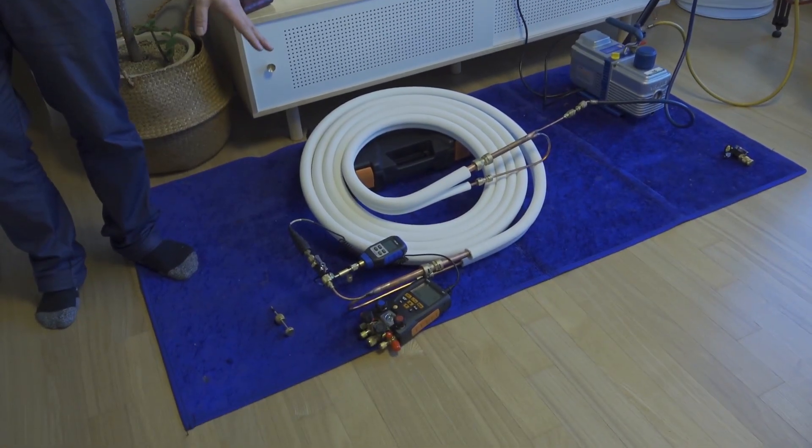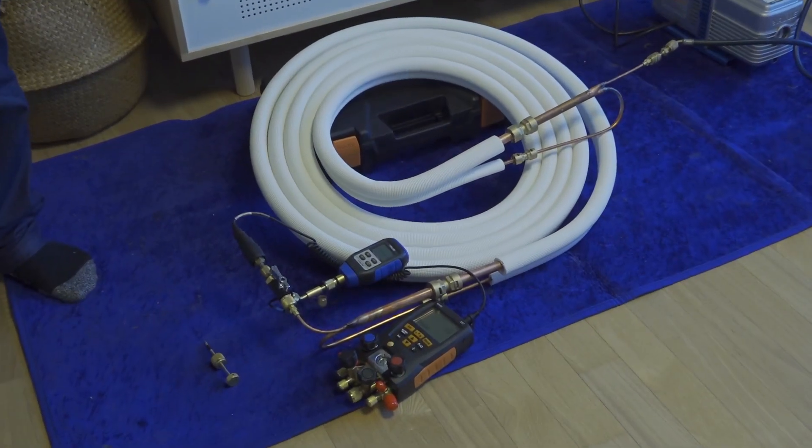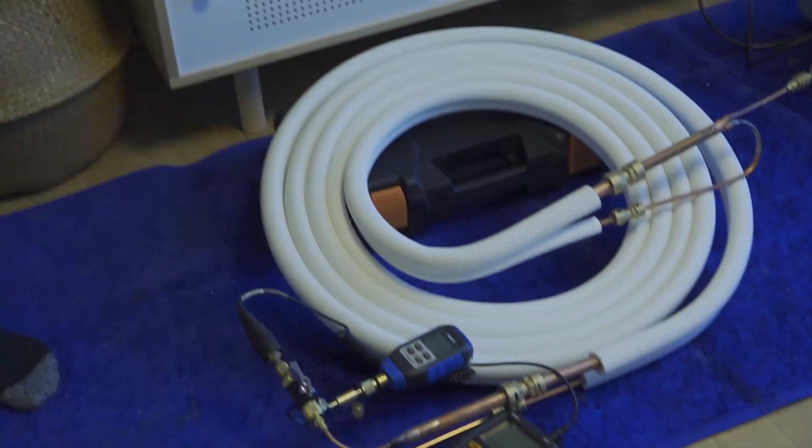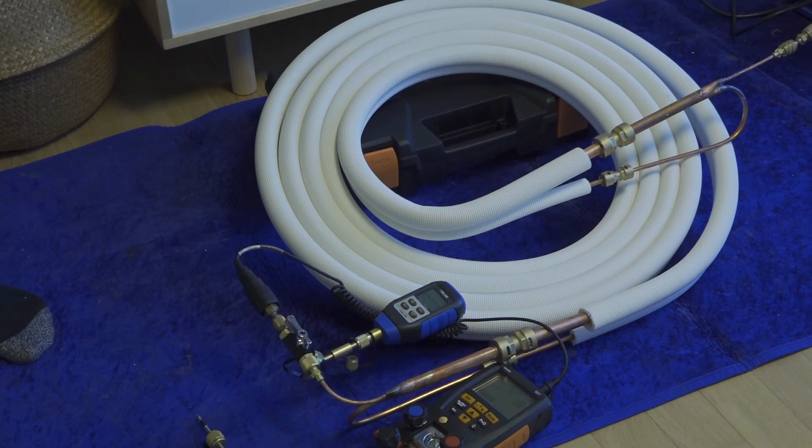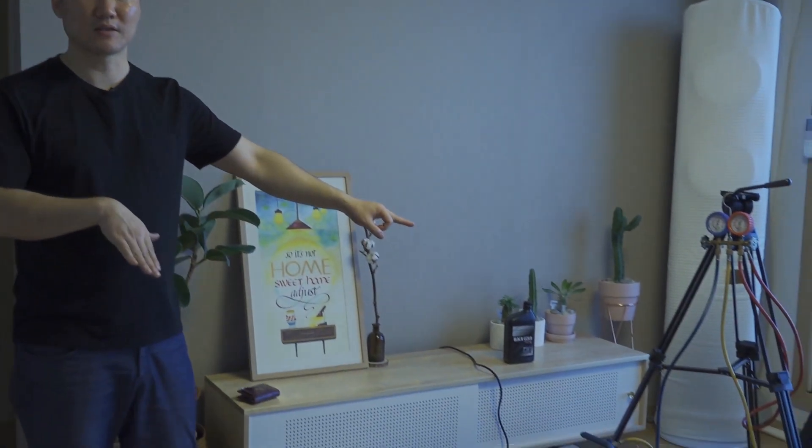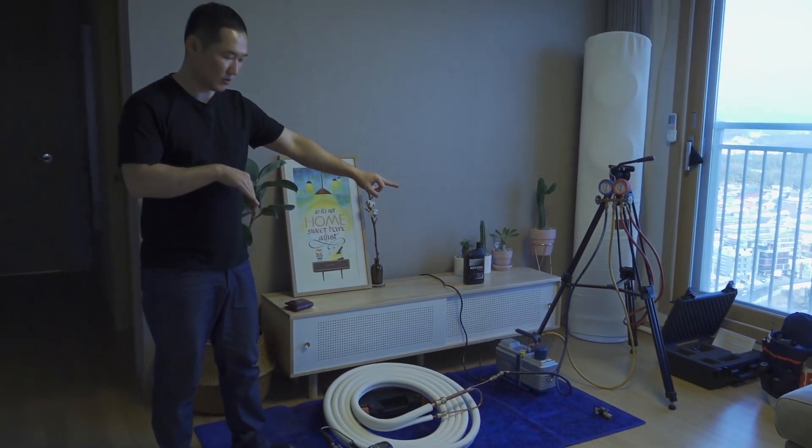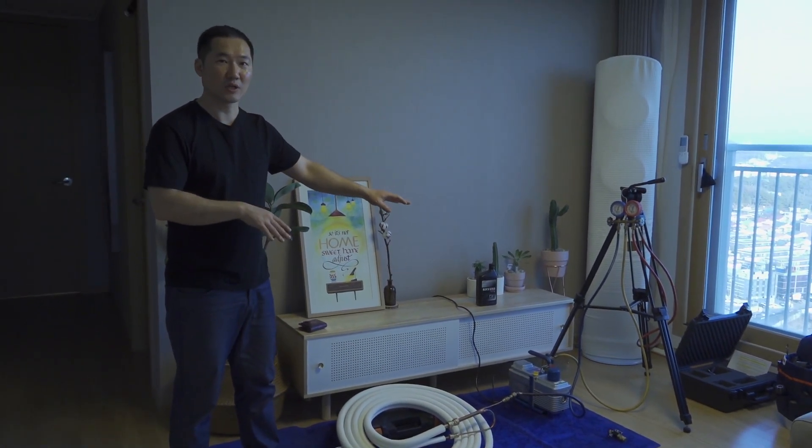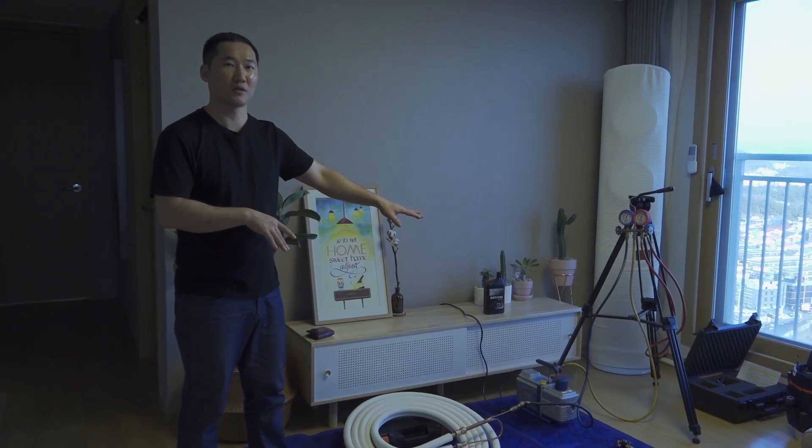I've connected two digital vacuum gauges right now. I want to see how much difference there is between the two. So today I'm going to test using a manifold gauge to pull vacuum and using a high vacuum hose to pull vacuum. And I'll check how much difference the digital gauges show between the side where we're pulling vacuum and the far end.